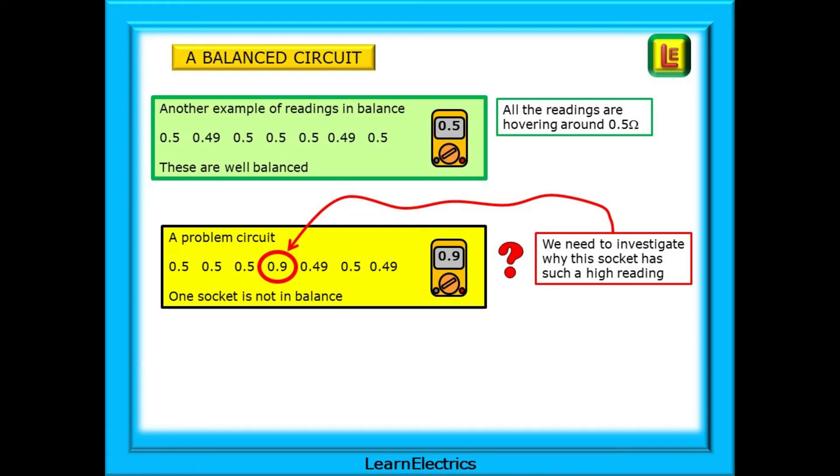But the yellow box shows a circuit with problems. One of the readings is quite clearly out of balance with the others. At 0.9 ohms, when all the others are about 0.5 ohms, something is wrong with the cabling to that socket or the socket itself, and we need to investigate and resolve the problem before moving on.